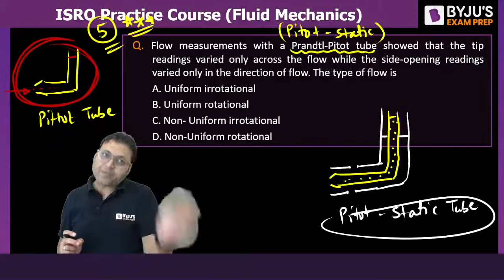Now, if there is an outer covering, another tube covering this pitot tube, then we call it a pitot-static tube, or we can call it Prandtl's pitot tube, because Prandtl developed this tube. So why is it used? Because the pitot tube only measures the stagnation pressure, so we need to measure the static pressure again using some other instrument like a piezometer or pressure gauge. We require the stagnation pressure and the static pressure, then we subtract these two and obtain the dynamic pressure, and dynamic pressure gives us the velocity. That is how this instrument works.